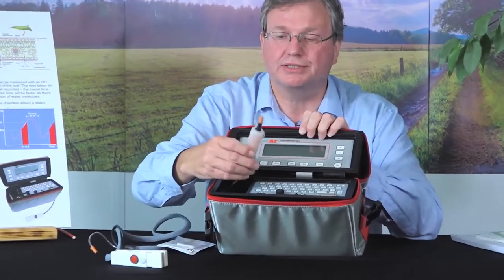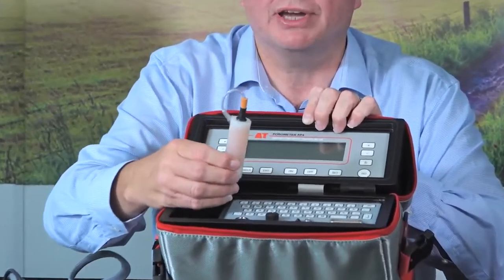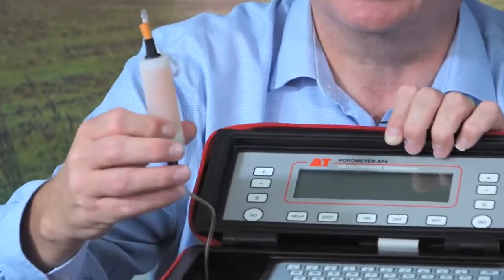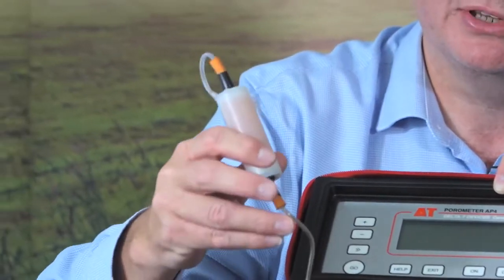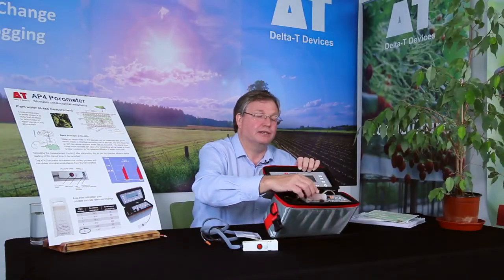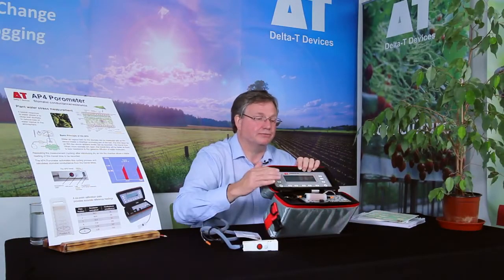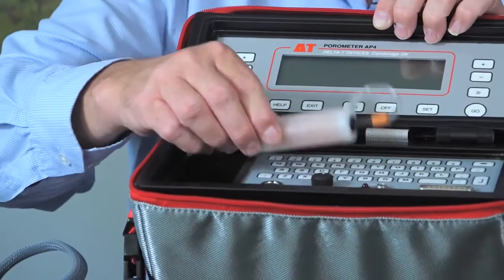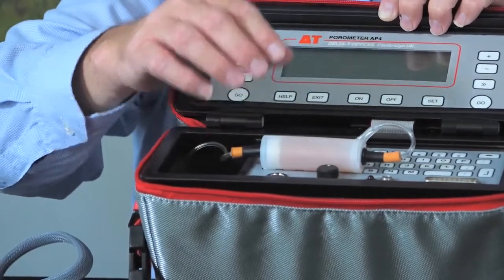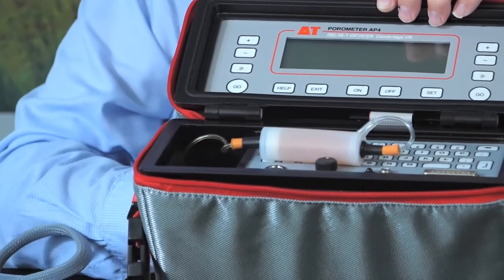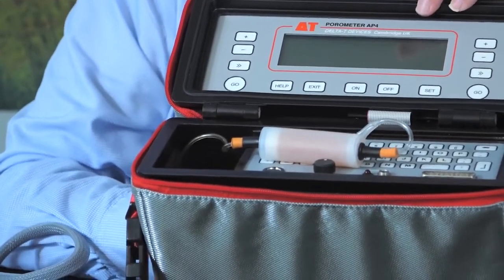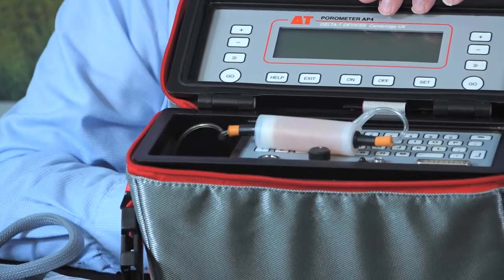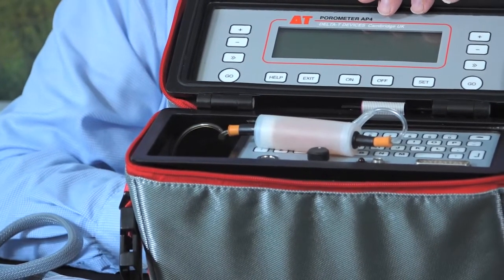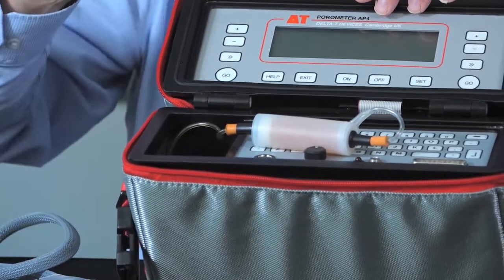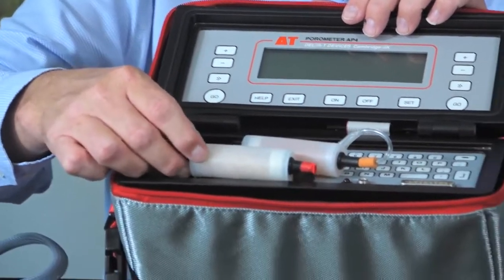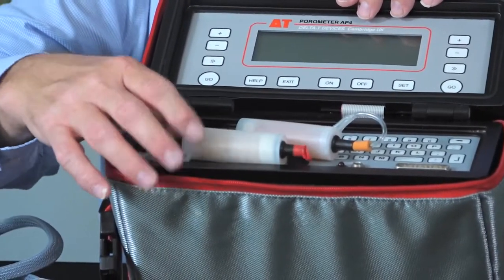Inside this compartment is also a canister, and this canister contains the silica beads which are used to dry the air which is pumped through the head. So it's connected to the main chassis with this tube, and then another tube going to the head where the dry air goes through. This is new silica gel. As it is used, it absorbs more water and becomes less effective. So it's always a good idea to check you have new silica gel inside the canister. This is old silica gel that needs to be replaced.